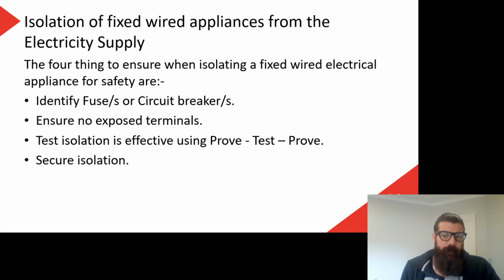So, isolation of a fixed wired appliance from the electricity supply. When we're talking about fixed wired appliances, we've discussed this before, something like a heated towel rail or anything that is permanently connected to the supply. There are 4 things that we need to do to ensure that when isolating a fixed wired appliance for safety, that we do it right. First one is identify the fuse or circuit breaker. So we need to find out which circuit breaker it is that we need to turn off.